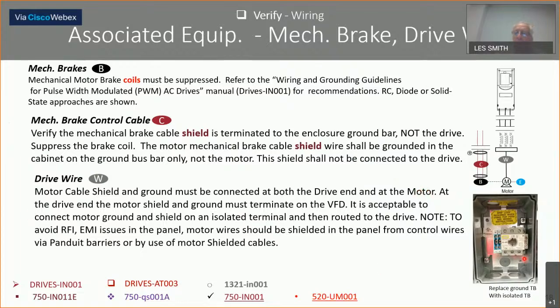And show you a field disconnect out here, and I've plagiarized it here. I put isolated terminal blocks here. Normally you would find a terminal block in there that would be yellow and green, and then it would clamp right onto the ground. And you notice this particular disconnect here has a metal backplate here that goes to the conduit here and up to here, and probably is connected to these terminal blocks here. I don't want that shield to get grounded anyplace else besides at the drive and at the motor. We will create ground loops. So just move the ground wire out around or change the terminal block to a non-grounded one and use it.